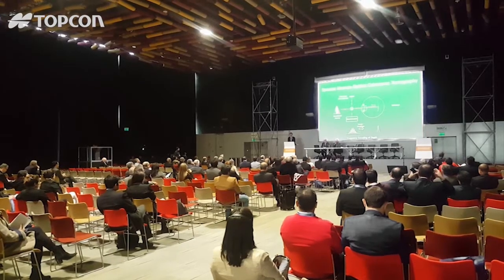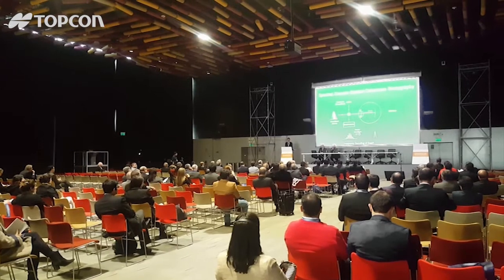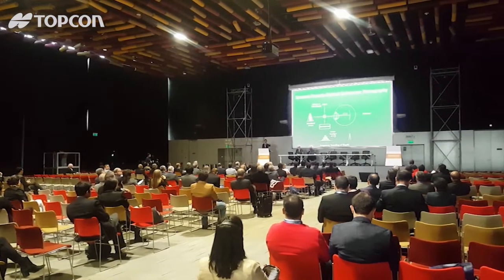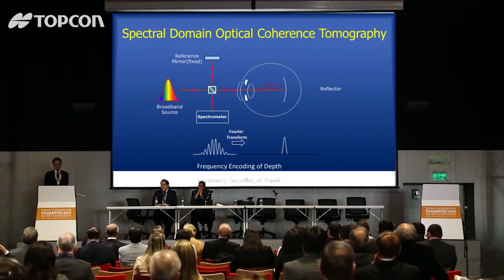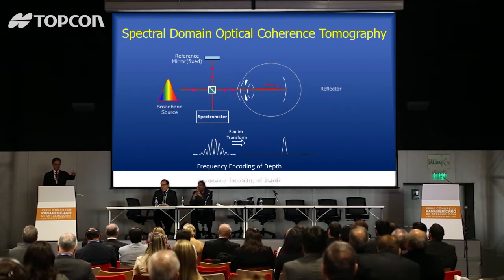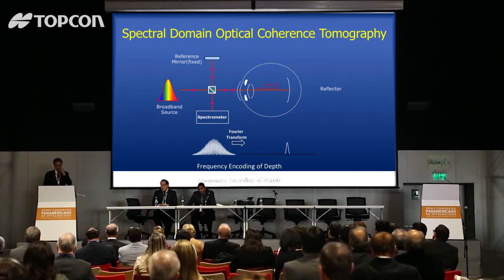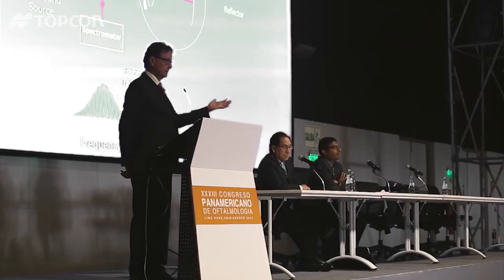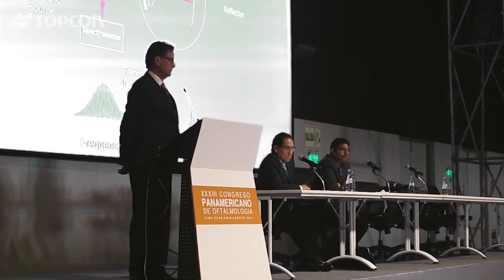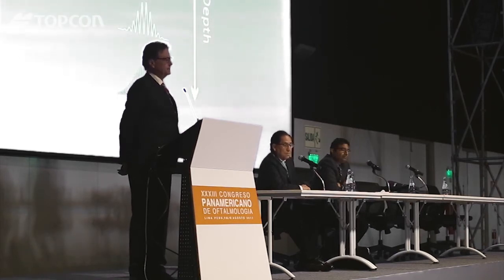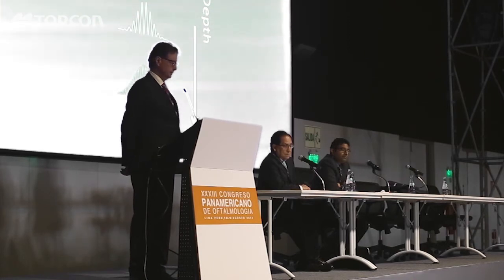The interferogram can be decoded with a Fourier transform to make a kind of a blip, and that blip represents what's reflecting light. If we move back so there's a difference between the arm lengths, the interferogram has a higher frequency. So there's a depth encoding of how things reflect inside the eye. That's the ingenious part of spectral domain OCT — depth encoding in terms of reflections and interferograms produced.